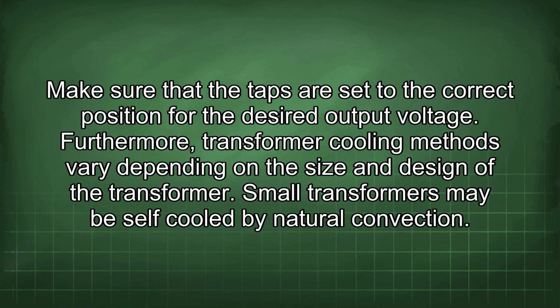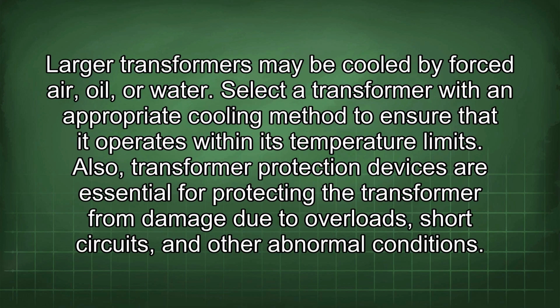Furthermore, transformer cooling methods vary depending on the size and design of the transformer. Small transformers may be self-cooled by natural convection. Larger transformers may be cooled by forced air, oil, or water. Select a transformer with an appropriate cooling method to ensure that it operates within its temperature limits.